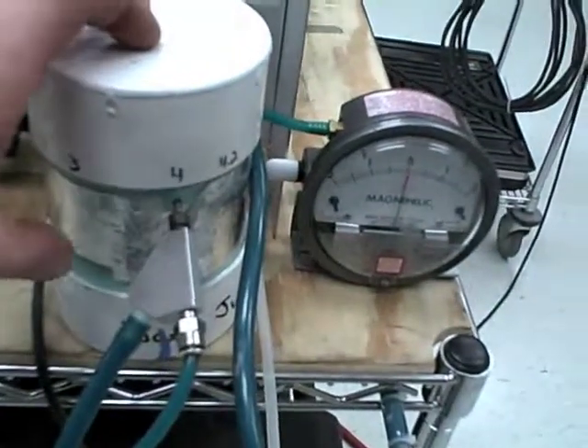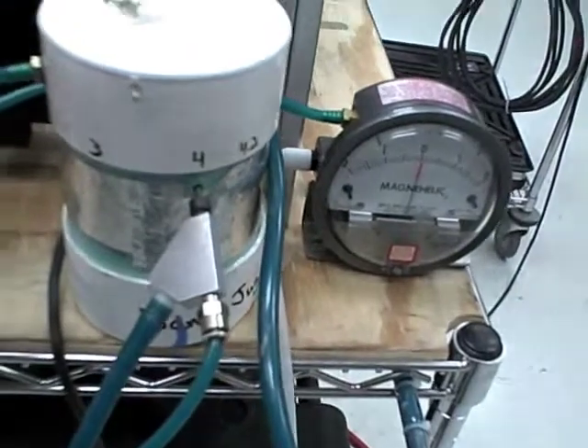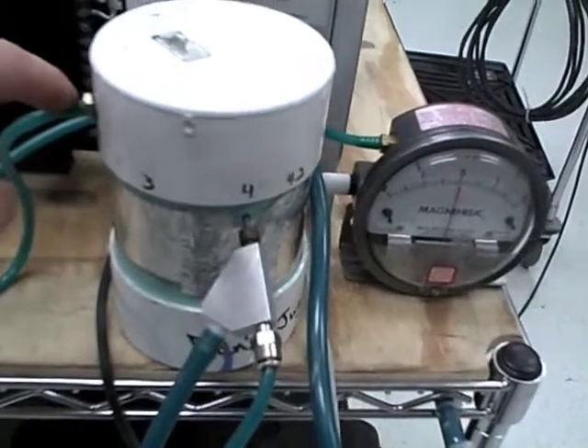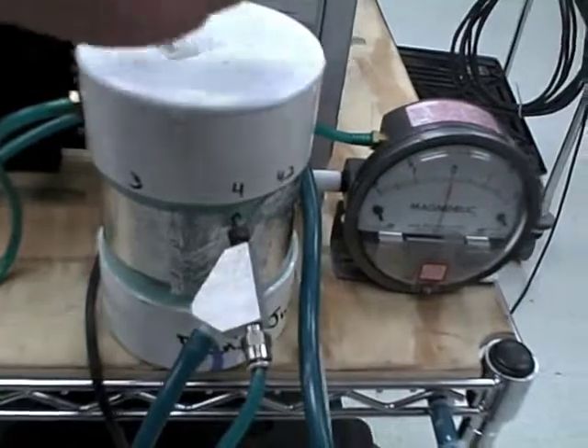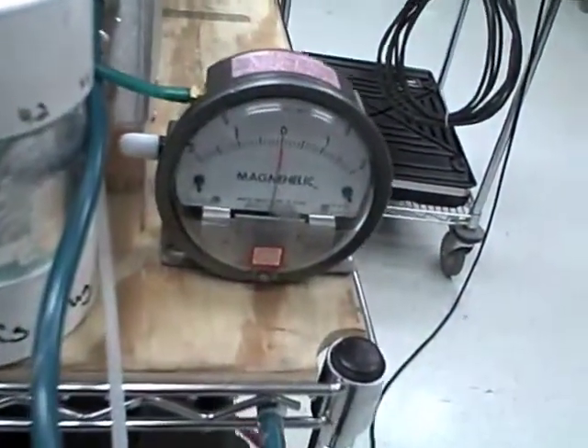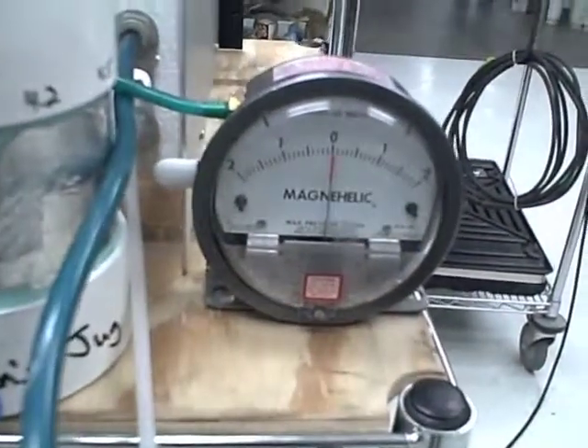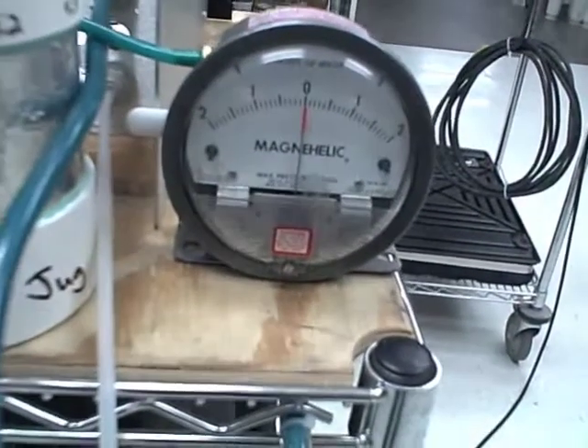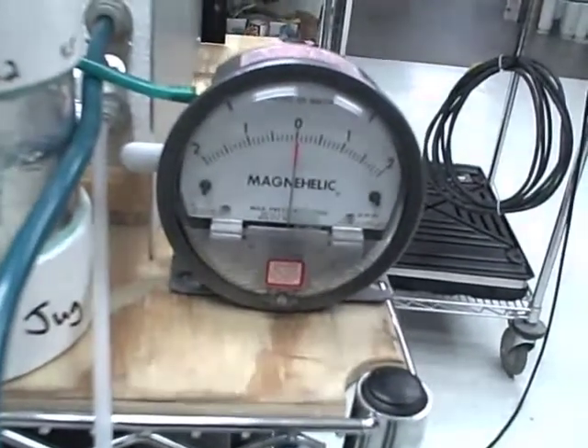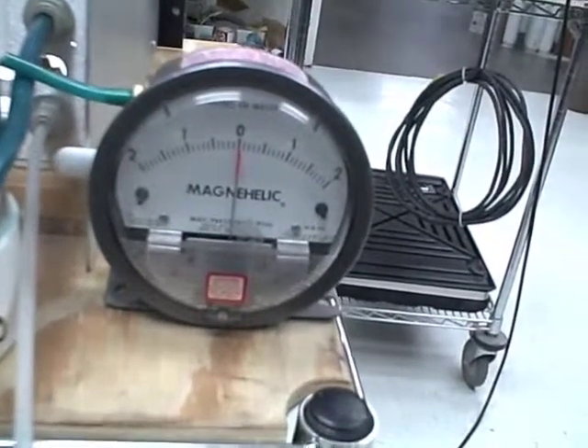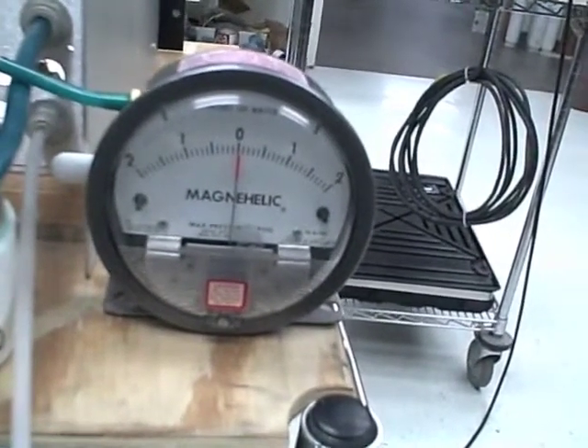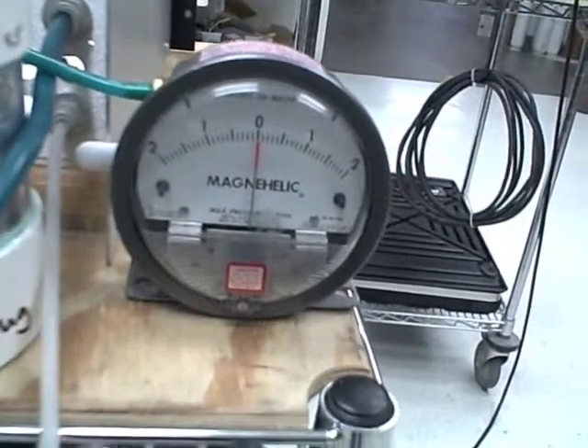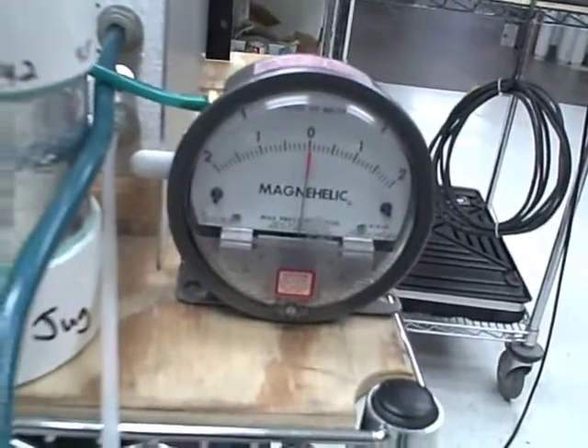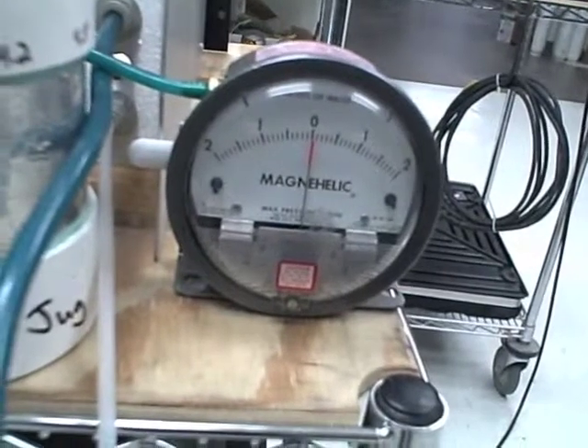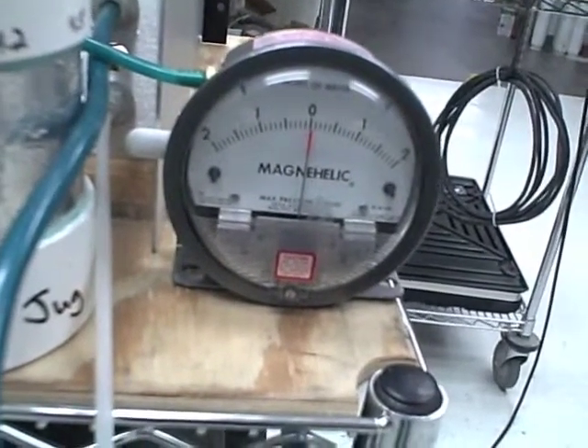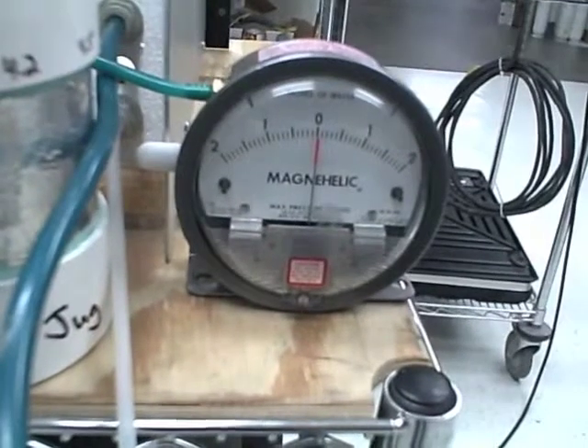So you can just take a piece of PVC with a couple ends on it, a couple caps, and then some kind of a brass nipple or something where you can connect it to the magnehelic. What the magnehelic does is it actually shows us what the internal pressure is inside this test jug, and it's a -2 to a +2 range magnehelic, and that's in inches of water. And what we want to do is have just a little bit more argon going in to the unit than we have vacuum pulling out.